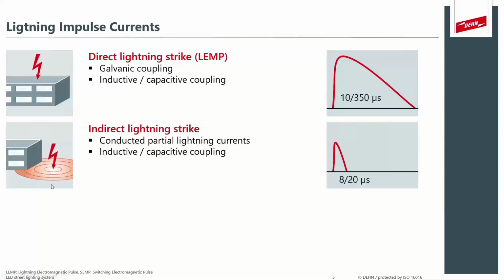Lightning can also strike in the vicinity of 500 meters around your building, or even 2 kilometers away from your overhead lines or power lines. That lightning strike that terminates onto ground level then causes a mutual inductance or an induced effect over the lines of the structure, 500 meters to 2 kilometers away. That induced lightning current or surge current is then characterized by an 8 by 20 microsecond wave shape.